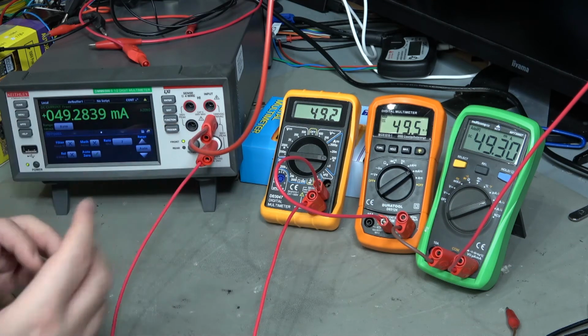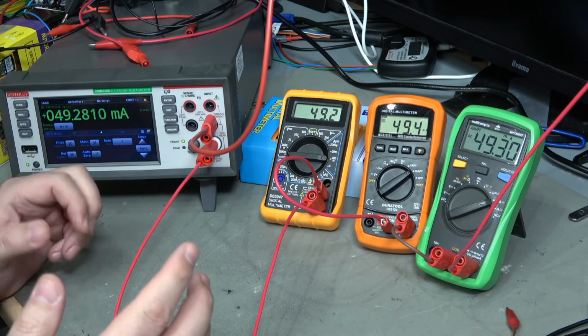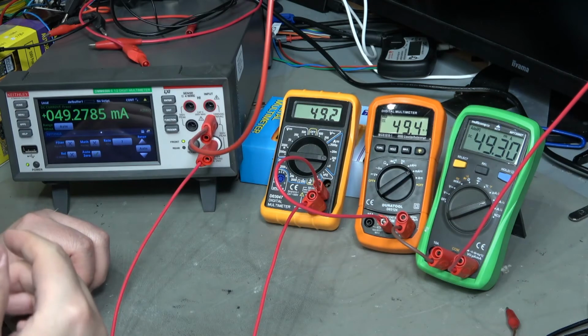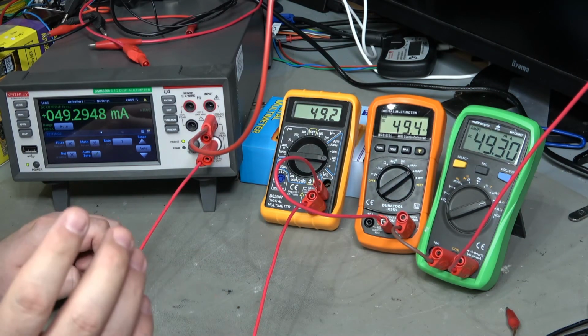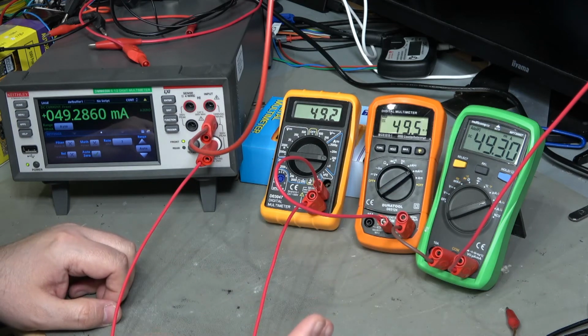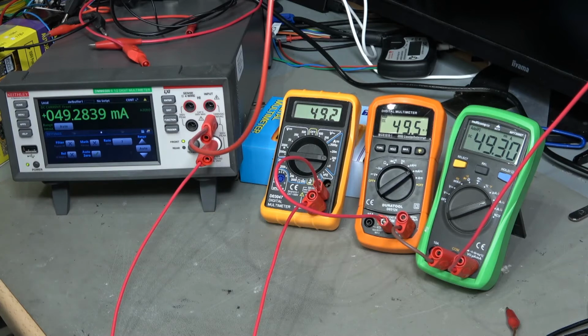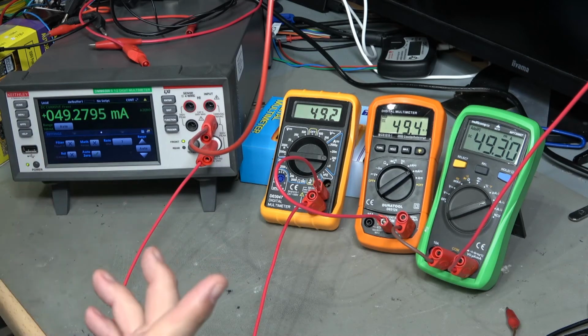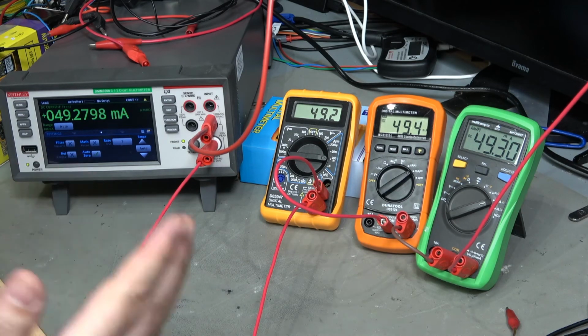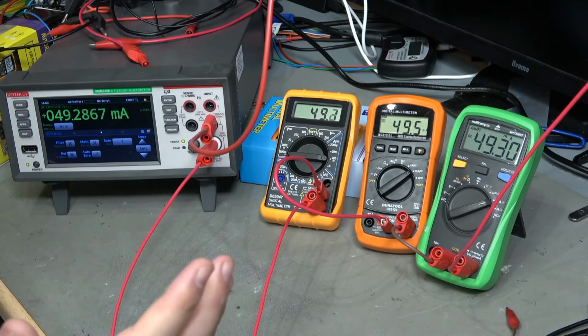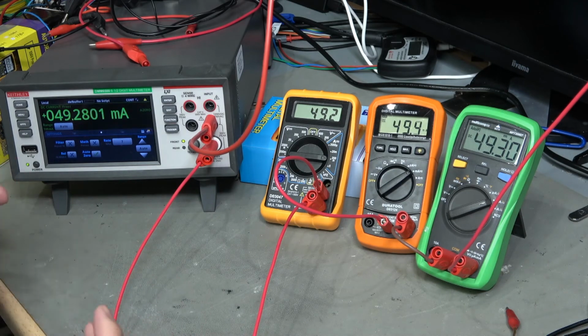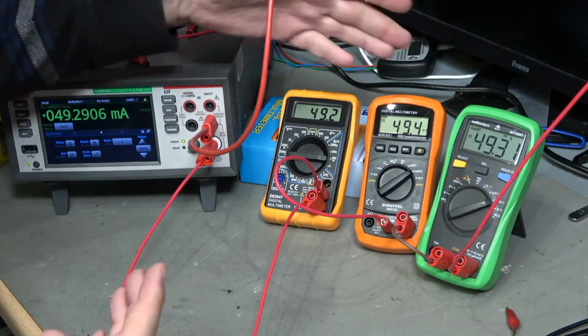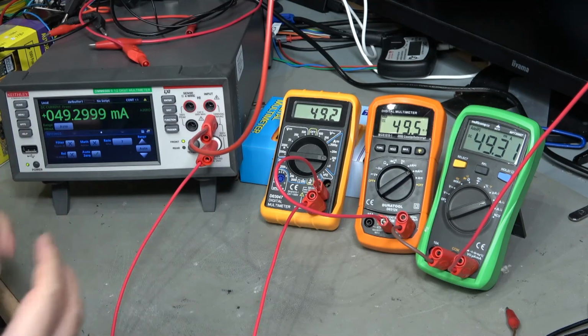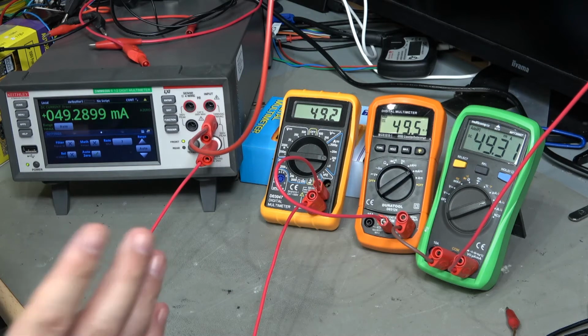And this kind of illustrates the thing that we're to some degree talking about. The current load is programmed for 50 milliamps. It says it is drawing 48, but in actual fact it's drawing 49. So that means it's one digit off in what it's reading, which is 1 milliamp. It's got a 4-digit display on the current load. So even the current load, which is several hundred pounds, the last digit can often be wrong. The last digit on these is always kind of questionable. You can never really trust it. It's always plus minus 1 at best, and if you look at the spec it could be plus minus 5, all sorts of things.